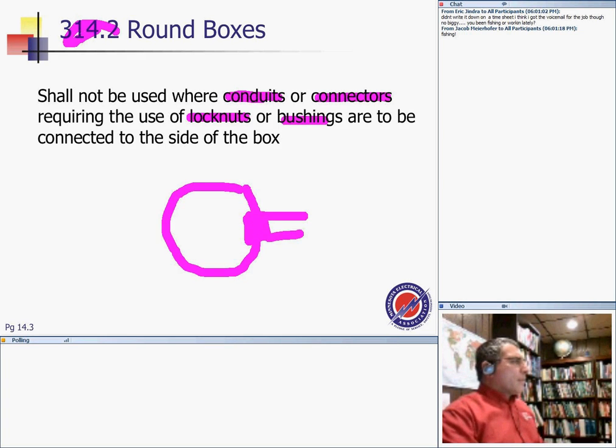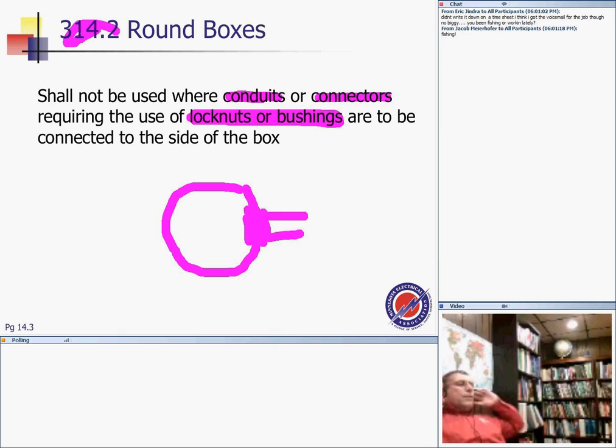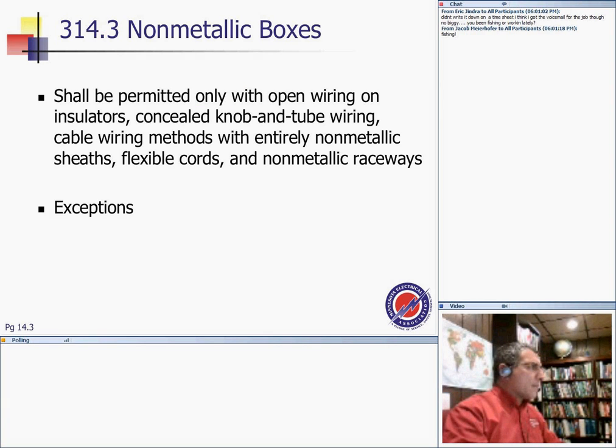So round boxes shall not be used where conduits or connectors require the use of lock nuts or bushings. Only the lock nuts and bushings are connected to the side of the box. So if you're using lock nuts and bushings with conduits, then you don't want to use a round box. Any question? A square box is your box of choice in this application. Any questions? So that's another important thing about boxes.